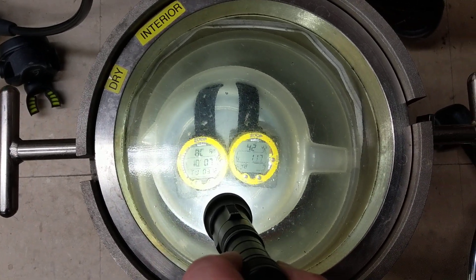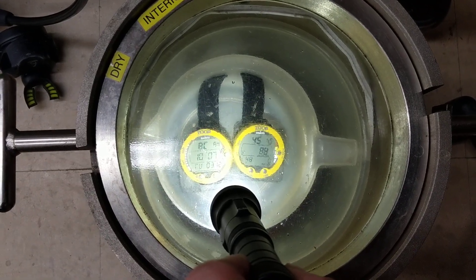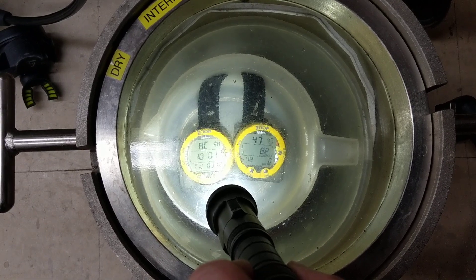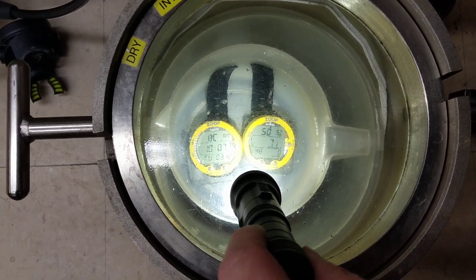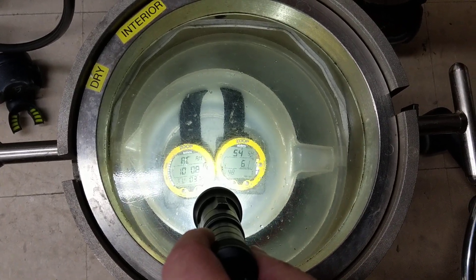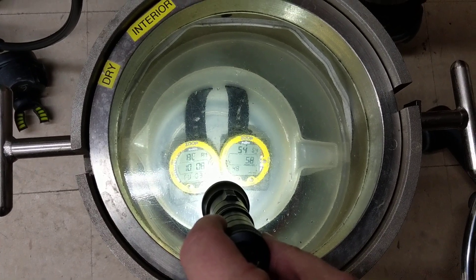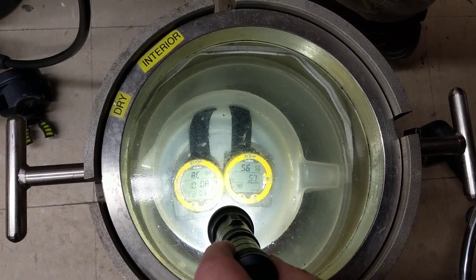The cracking noises are just the pressure building up — it's a little creepy, but that's okay. Unfortunately, one computer here looks like it's got some serious issues, and the other one is performing dead-on perfect, reading about 52 to 53 feet, which is exactly what we got on our master gauge. So we're going to let it stabilize and then take this down a little bit more.